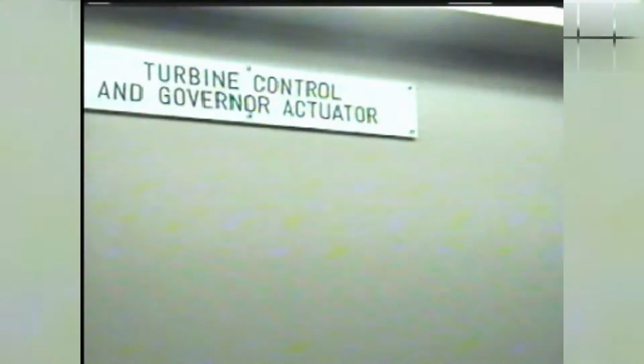The turbine is equipped with a single double-acting servo motor provided with adequate safeguard to prevent lifting of the regulating ring. The servo motor is provided with sufficient capacity to operate the guide vanes under all hydraulic conditions with the minimum oil pressure from the governor oil system.